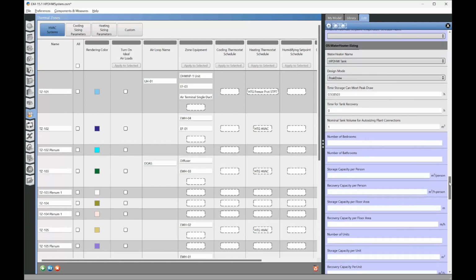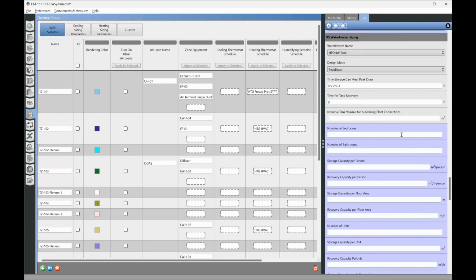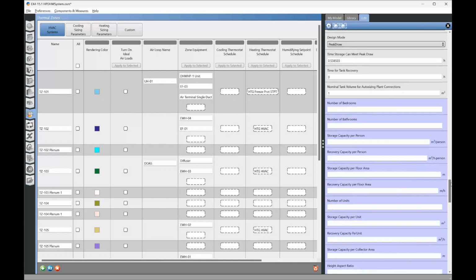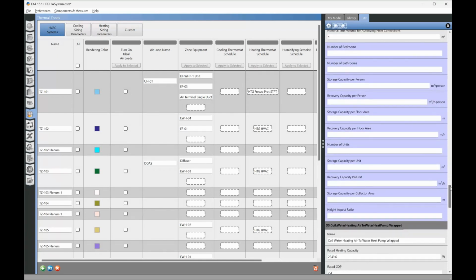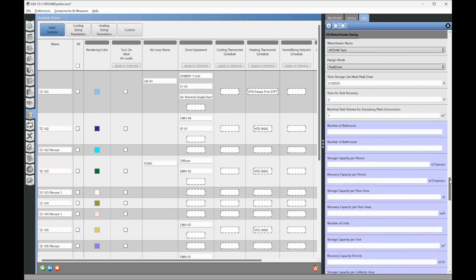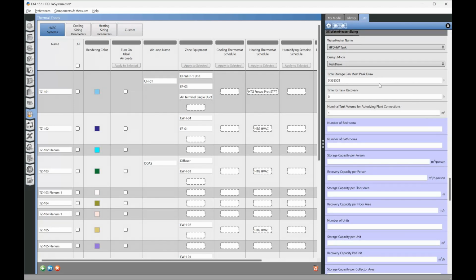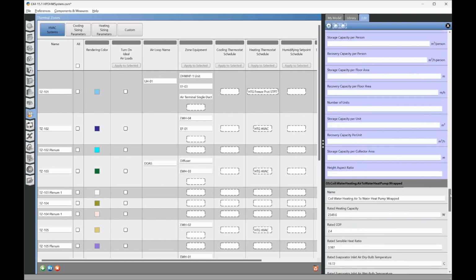And as you can see, this is a water heater sizing algorithm based on the number of people expected to use this. So this is normally for domestic water uses for lavatories and kitchen sinks and whatnot. But as I said, we don't have auto size on. We already hard sized the tank, so this information won't be used.